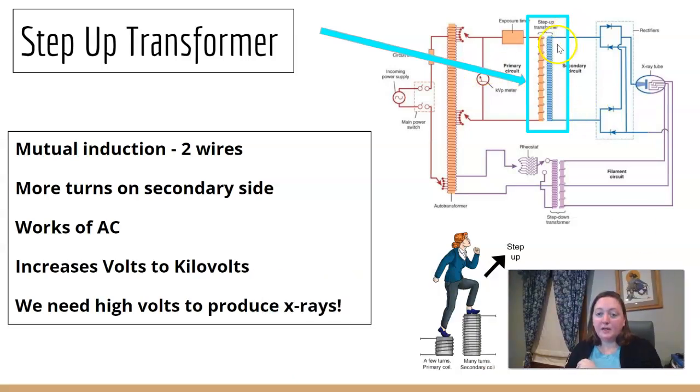The first one that we hit up here on the top is the step up transformer. And I want you to think it's right after the KVP meter. It's going to turn my volts into kilovolts. The step up transformer works off of mutual induction because there's two wires. So the step up and step down have friends. There's two of them. They have a primary and a secondary side. The step up means there's more windings of the coil on the second side than on the first side. It's increasing. So we're going to bump our volts to kilovolts up here.